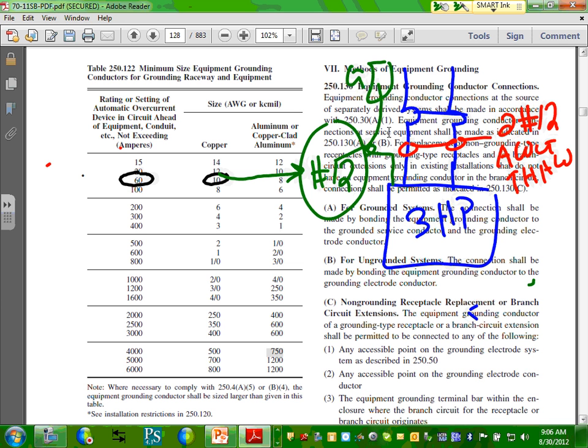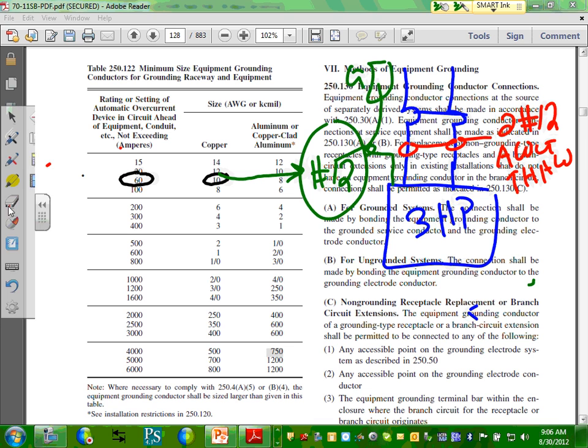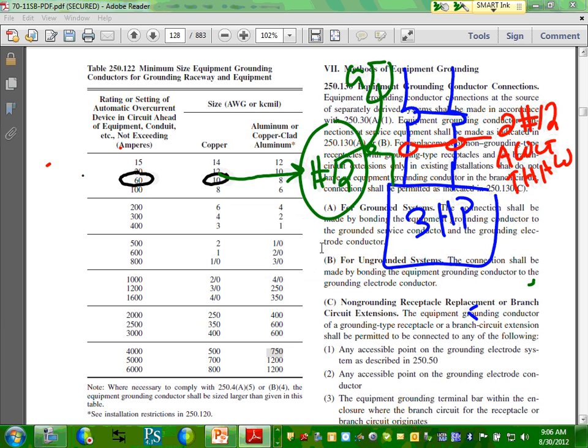Can I have a thumbs up that we fully understand that? And that happens only with motors, because the overcurrent protection devices are way oversized, you end up with a bigger grounding conductor than the phases. Doesn't make sense, right? So the code in Article 430 allows you to go down to the size of the conductor. Okay, so everybody knows why the conductor is going to be number 12 now? Now everybody knows how to use this table too. This is how you pick the ground based on overcurrent protection device.